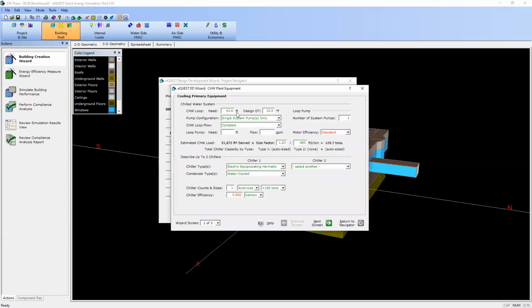And so here I can define a whole bunch of stuff about my chilled water system. Most important one being, what is my chiller efficiency in kW per ton? And that is at an AHRI certified condition. But if I plug in 0.6, eQuest is smart enough, or has the built-in tools, to estimate a varying efficiency based on the varying conditions that you might see over a year.